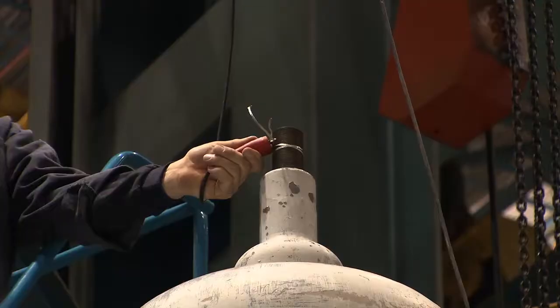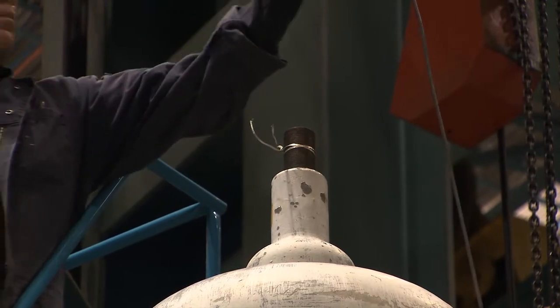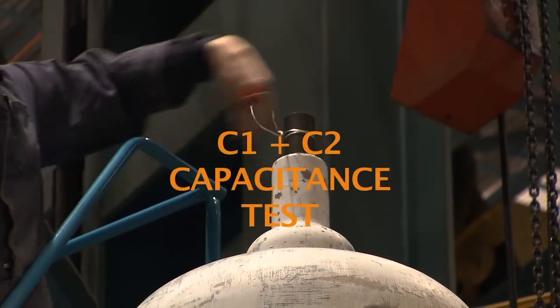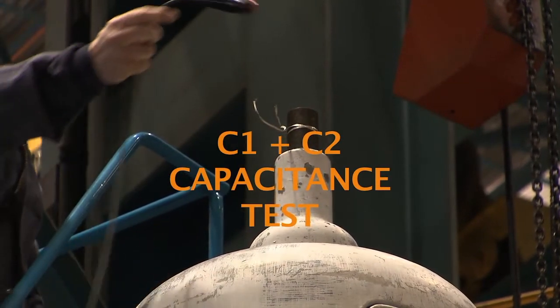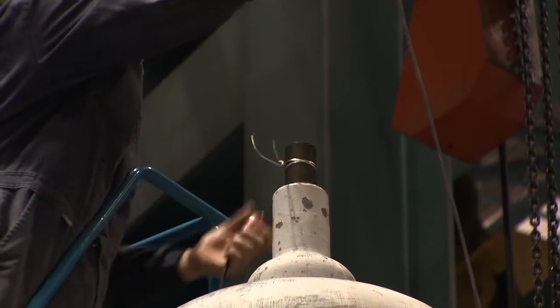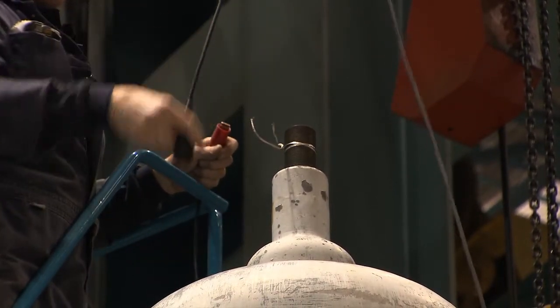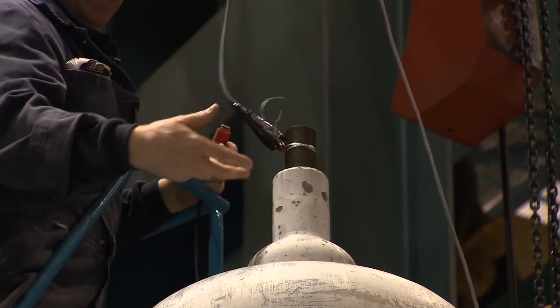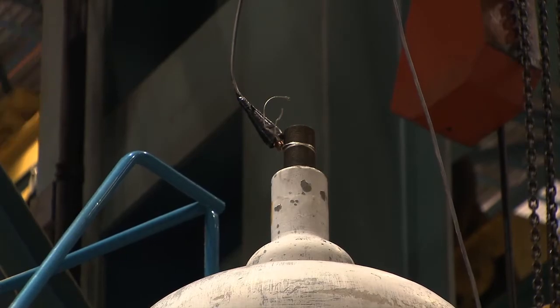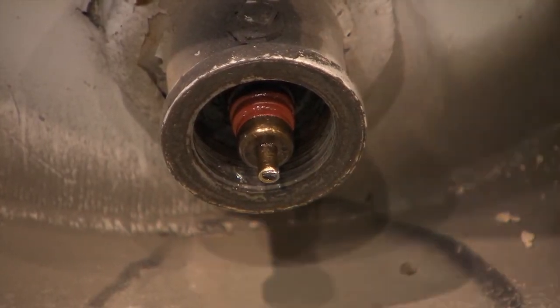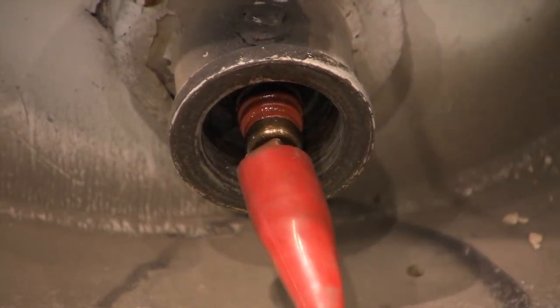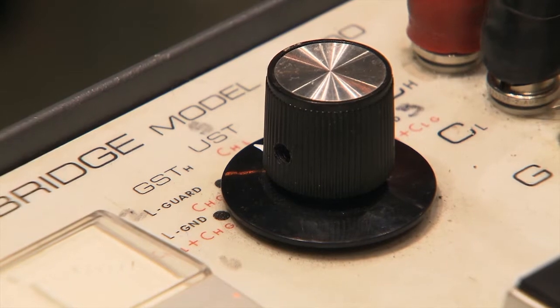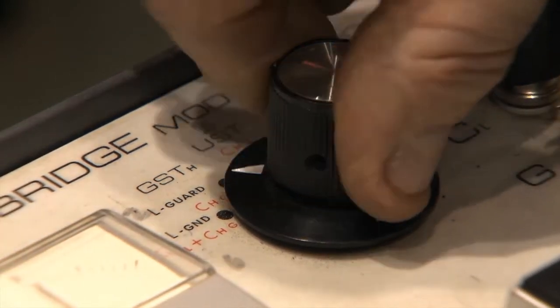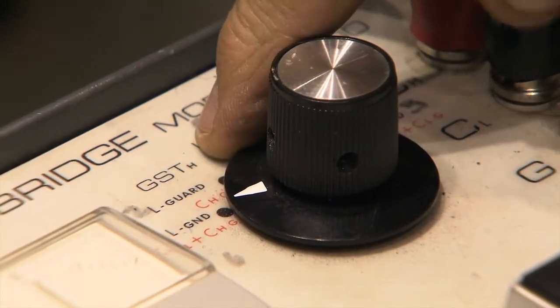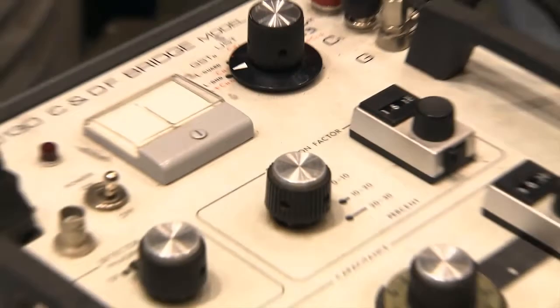The next test is the low ground GST test, where GST stands for Grounded Specimen Test. It is commonly referred to as the C1 plus C2 test. Disconnect the end of the cable that sends out the electric current, the red lead, from the pure copper strand at the top of the core conductor, and connect the lead that was connected to the cap tap, the black lead, to the pure copper strand. Okay, now we're going to just switch this to low ground grounded specimen test. And then we're going to start the whole procedure over again exactly as we did with the first step.